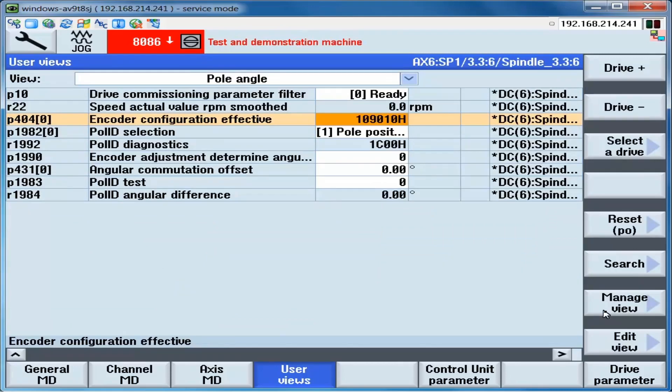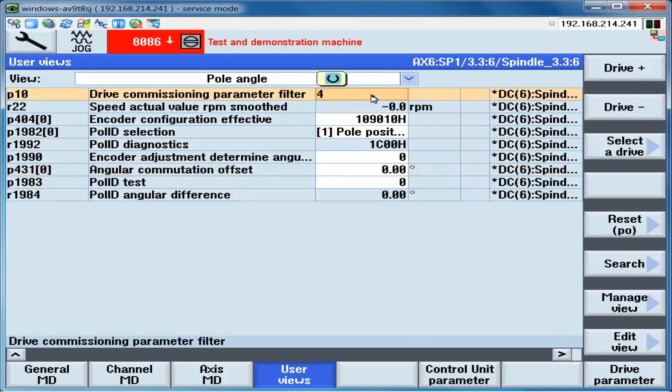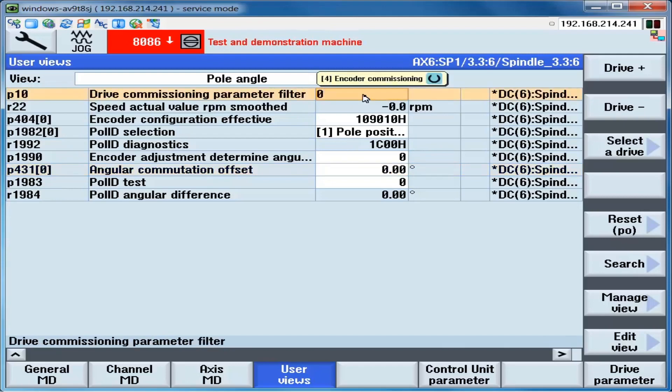Before beginning, it is recommended that P431 be set to a 0. If the drive had been previously operating, there will likely be a previous angle in P431. In order to set it to 0, P10 is set to a 4. P431 is set to a 0. P10 is set to a 0. And now the angle in P431 is 0 degrees before beginning.